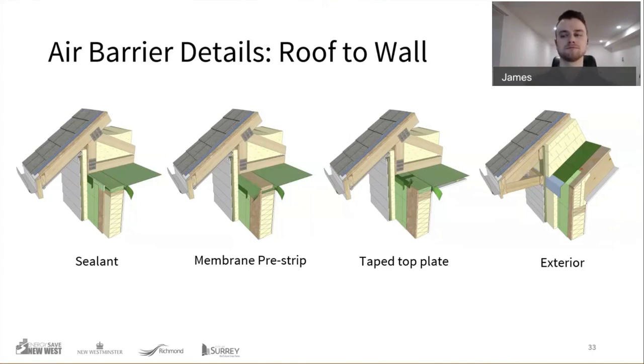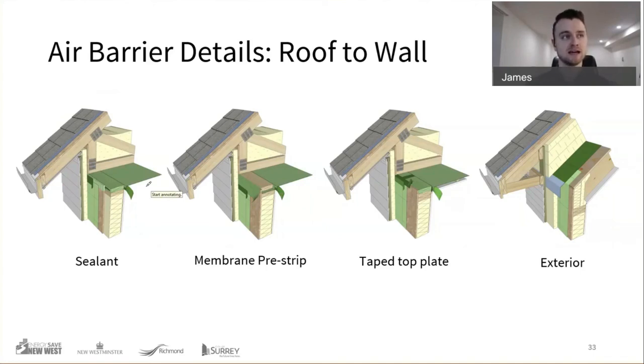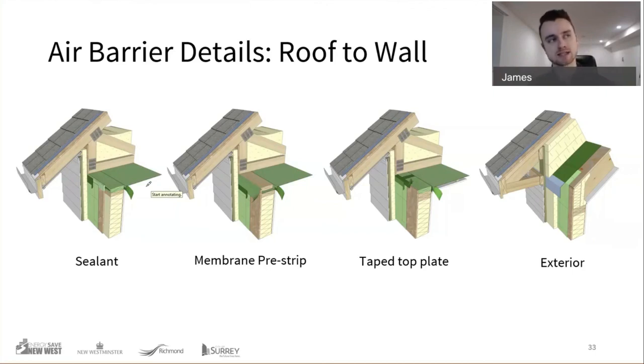Question: what are your thoughts on air sealant spray like Aero Barrier? From my perspective, we've seen it does work to improve and achieve air tightness, but I haven't seen it enough in person to know how it acts at large-scale construction projects. In general, we prefer to have details that are intentionally airtight — viewable sealed sealant and tape, very much airtight components making up the air barrier — rather than relying on an aerosolized seal approach. It does work, but an intentional air barrier from the get-go is generally how we approach it.